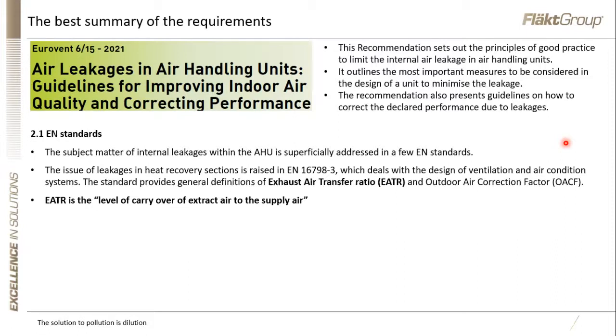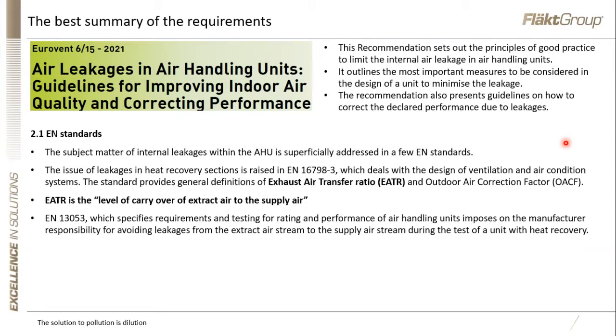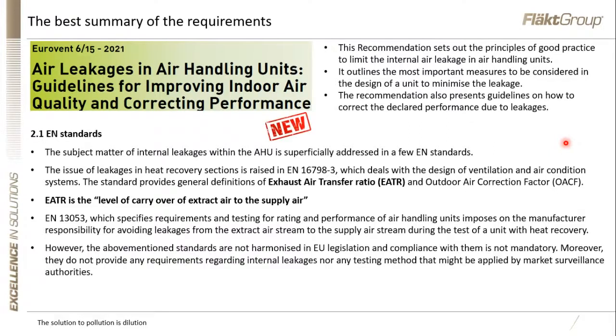In other words, the percentage of exhaust air that we recirculate back into the space. EN 13053 specifies requirements for the performance and testing of an air handling unit, and it imposes on us as a manufacturer a responsibility for avoiding leakages from the extract airstream. And we take that very seriously. However, the above standards are not harmonised in EU regulation, and compliance with them is therefore not mandatory. And there is no real objective testing method that might be applied by market surveillance authorities.